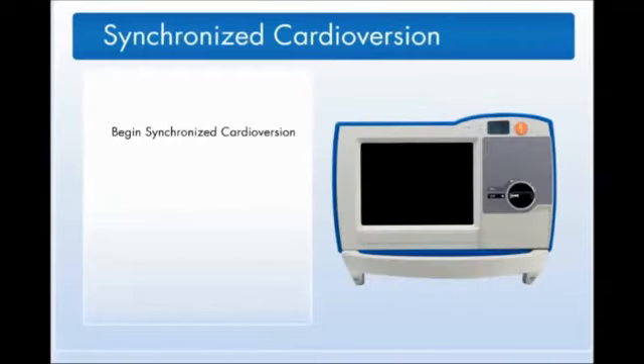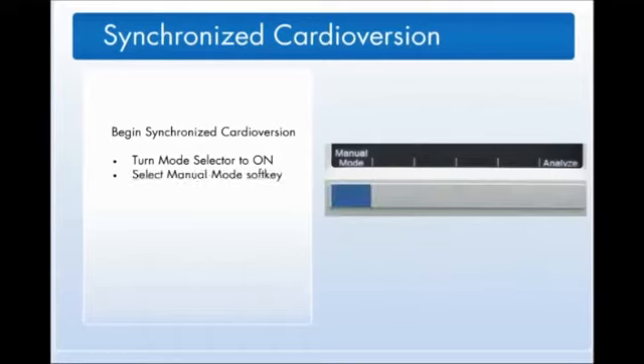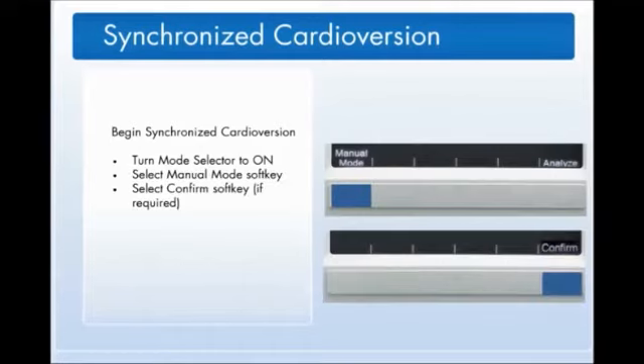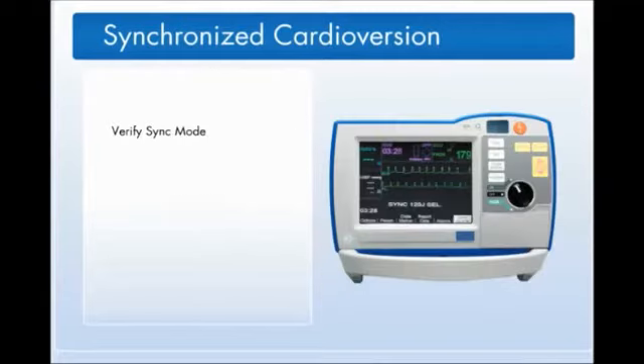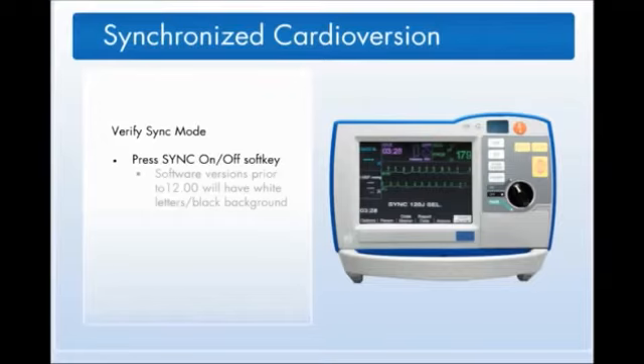When using the R Series Plus to perform synchronized cardioversion, you must first set the defibrillator to On, press the Manual Mode soft key, and then the Confirm soft key if required. You must verify the device is in sync mode. To do this, follow these steps. Press the Sync On-Off soft key.